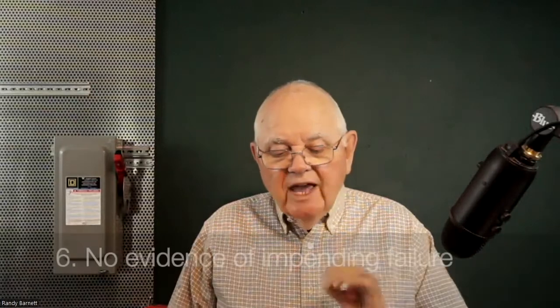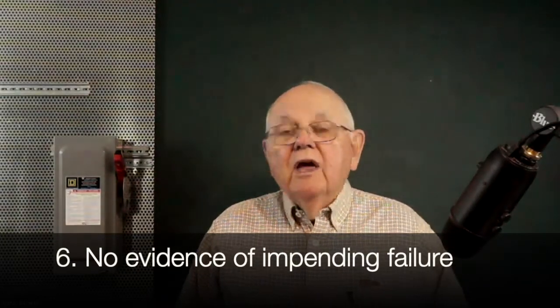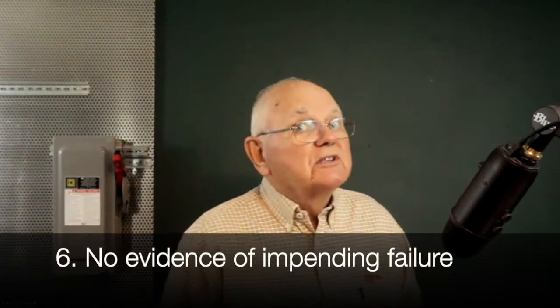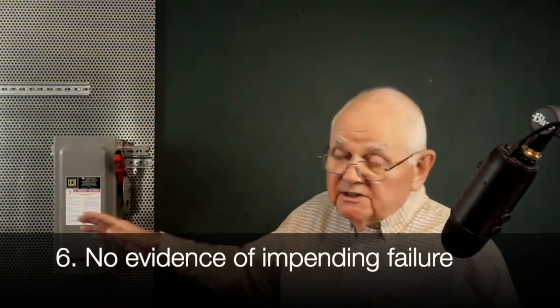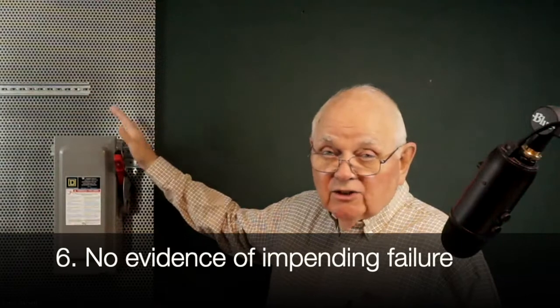And then the last item says there is no evidence of impending failure. So once again, that's a lot based on our experience, isn't it? I mean, we need to be able to look at this equipment and go, well, I don't see any burn marks on the outside. I don't smell any burnt insulation when I walk up to it. There's no water dripping on top of it. All of those items would indicate that maybe something is wrong with it. So the first thing I have to determine is, do I meet those 6 requirements? If I do, then I say the equipment is suitable for normal operation.